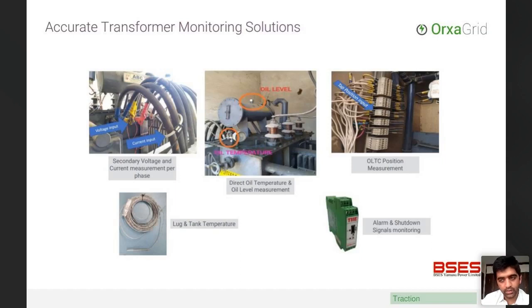For oil temperature, this was again something where we had to study a lot of different transformers that have been installed across the various discoms. What we traditionally understand is that a lot of transformers typically have spare pockets available, and by understanding the diameter and the thread sizes, we customize the fixture for installing the oil temperature PT1000 input into it.